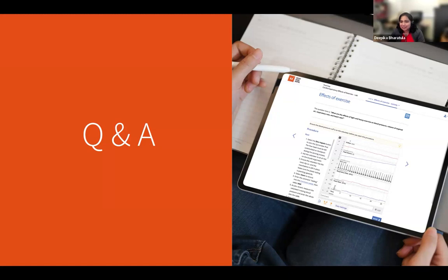Awesome. So now I just want to ask something technical. How do you calculate the dead space in case of longer tubings? I believe that's your area. We don't calculate it as such. We estimate the volume of the tube, the diameter and the length, and then just enter that into LabChart, I think.